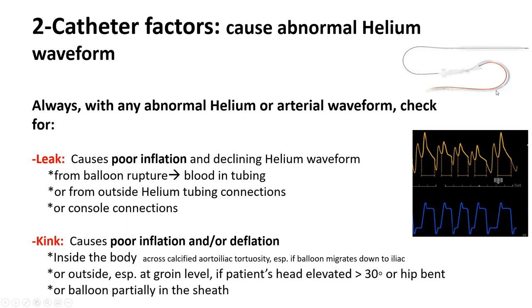Second cause, and maybe more common, is poor connections. So your connection of that helium to the tubing is not right, or the connection of the tubing to the console is not right, or the helium canister is empty. So you check the connection along with your nurse. So those are the second causes for leak.